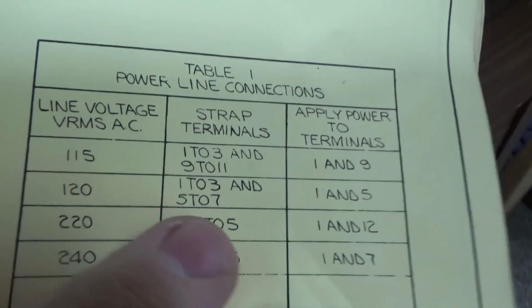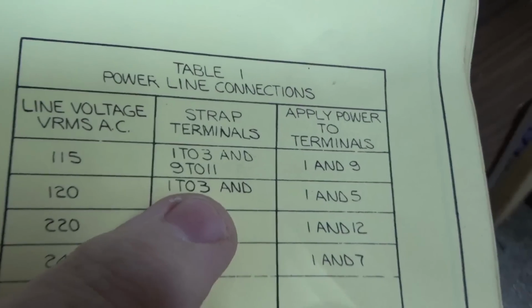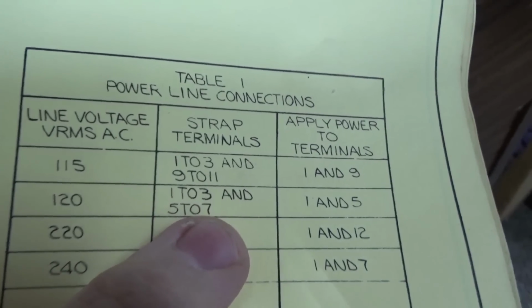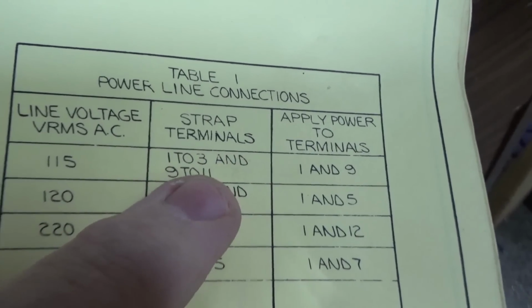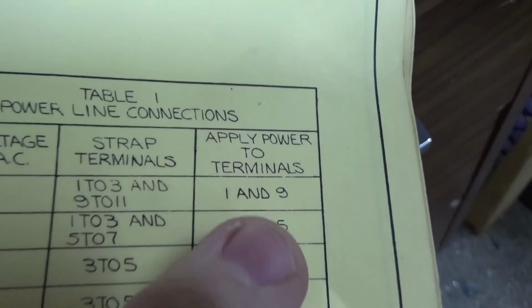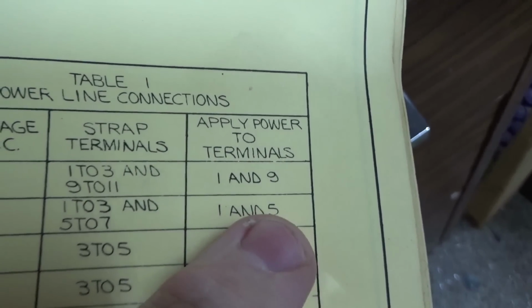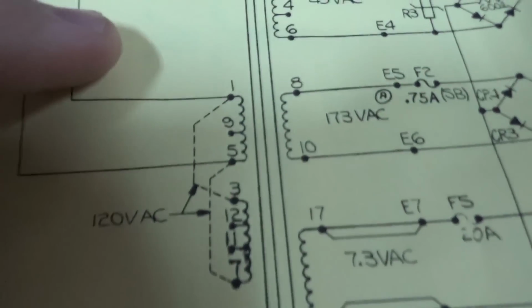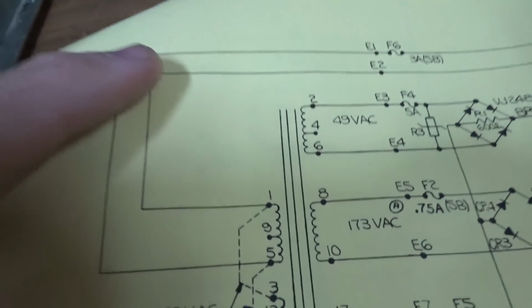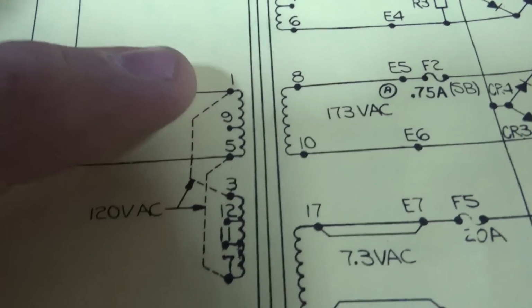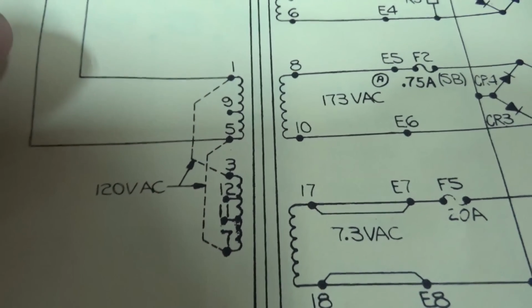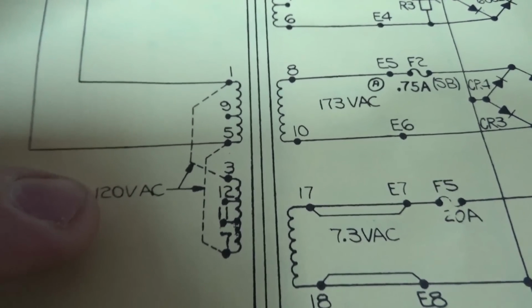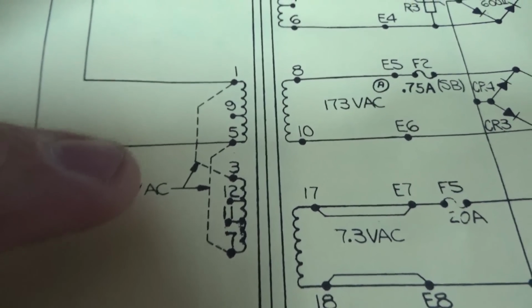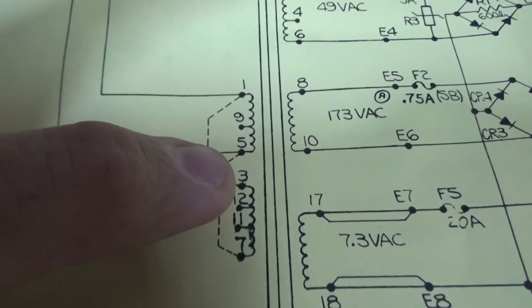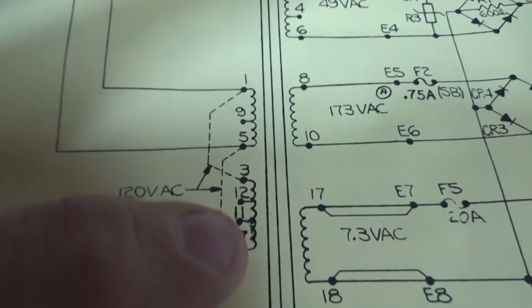The way you do that is you tie 1 and 3 together and 5 and 7 together, instead of 1 and 3 and 9 and 11. Then you hook power to position 1 and position 5. They're actually showing that here. The power's coming in at 1 and 5, and they're saying that if you hook it up for 120, 1 and 3 should be connected, and 5 and 7 should be connected.